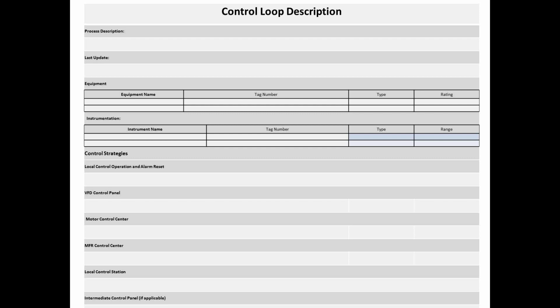The last update: a lot of times when these are being created, they go through numerous revisions. So this tells you the latest date, and sometimes the latest date and time, of the control loop description, so that the programmer can make sure they're working on the latest one. It starts out by listing all the equipment that's being used on the control loop drawing. It talks about all the instrumentation that's available.